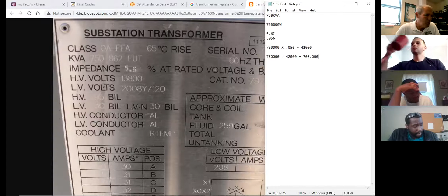Now watch what I'll say in the question on the test or quiz. If I ask what are my wattage losses with this transformer nameplate, is my answer right now in watts? Yes, it's still in watts, I haven't converted it. If I ask what is the true kVA, I need to move over and get rid of the 10, 100, 1,000. 708 kVA, there you go. 708 kVA is my true kVA.